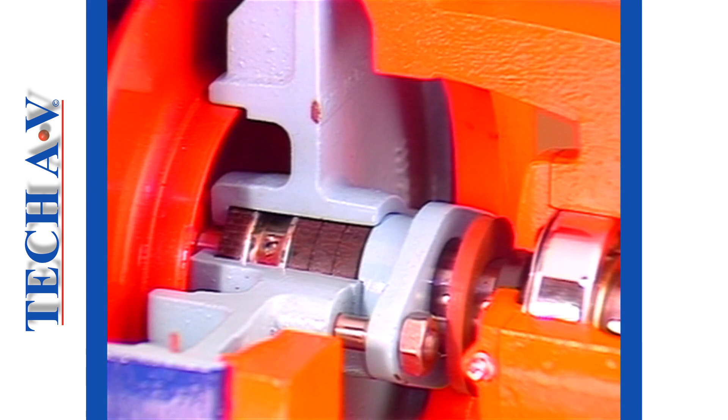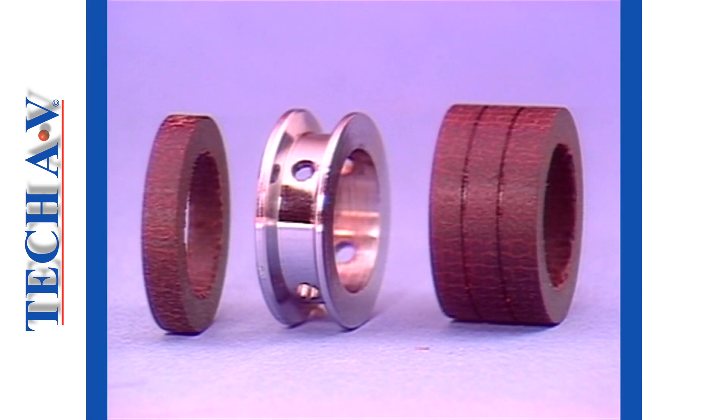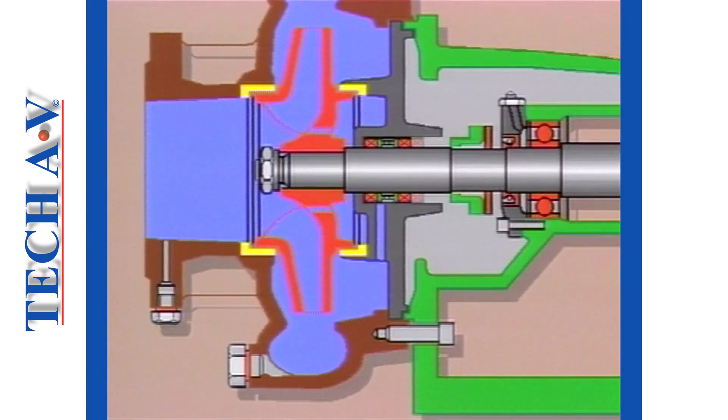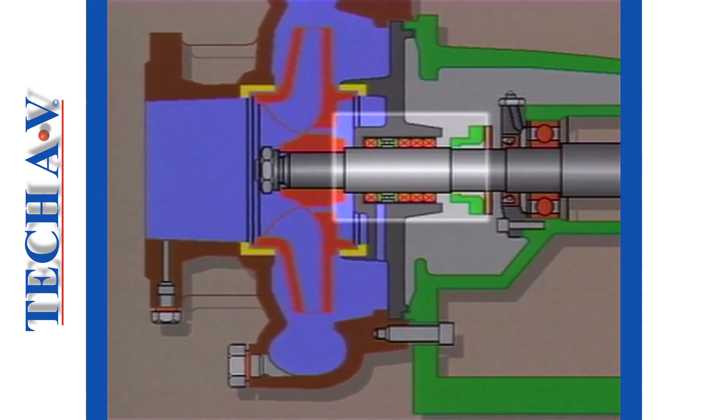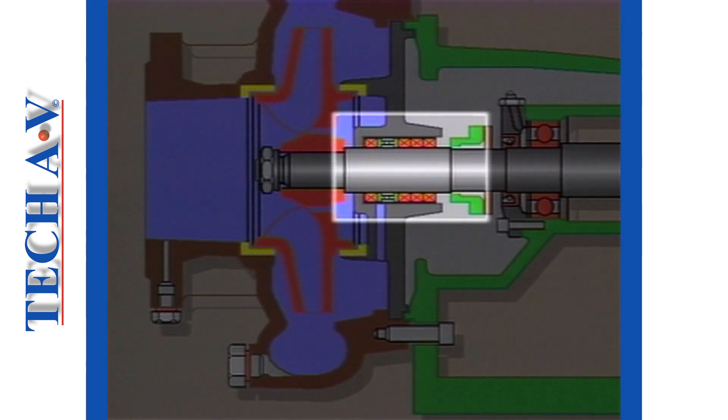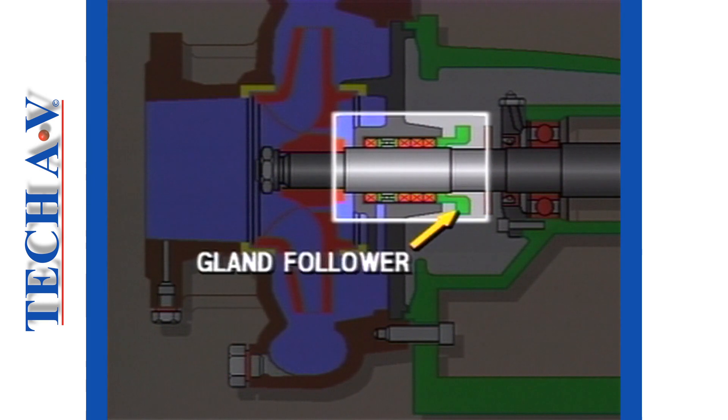The gland cover contains the sealing components, which are necessary to prevent air from entering the system via the impeller shaft. In the pump type being discussed, the seal comprises soft packing rings and a lantern ring, all of which are contained in the stuffing box. The packings are held in compression with a gland follower.